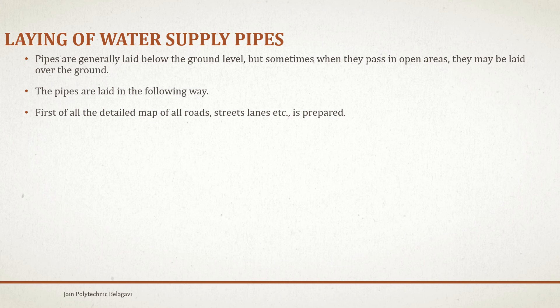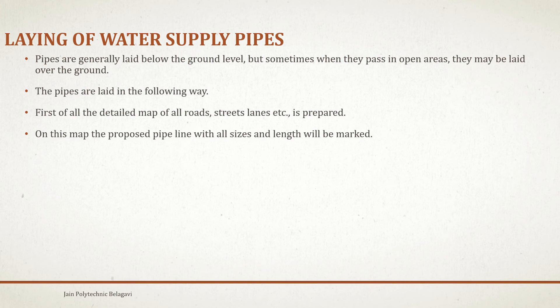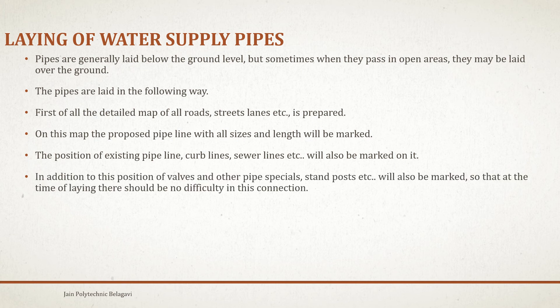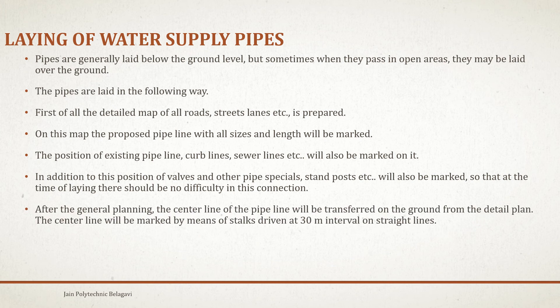First of all, a detailed map of all routes, street lanes, etc. is prepared. On this map the proposed pipe line with all sizes and lengths will be marked. The position of existing pipelines, curb lines, and sewer lines will be marked on it. In addition, the position of valves and other pipe specials and standposts will also be marked, so that at the time of laying there should not be difficulty in the connection.